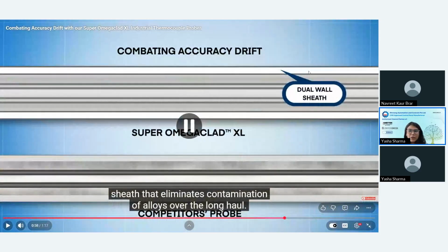So we have a dual wall sheath for this one. It also prevents the accuracy drift. A single wall will have an insulation failure and you won't get the accuracy.